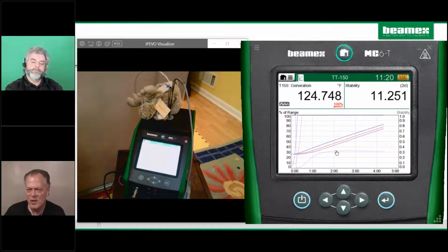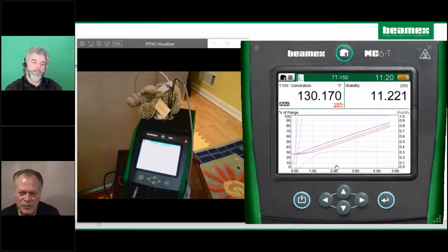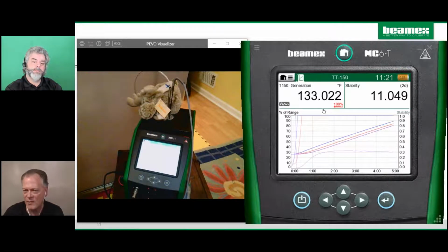So we've been talking now for 4 minutes since we made that first recording, and we're getting there. We're now seeing 100% on the graph. We're at 100, almost 130 degrees. So everything's moving along pretty good. We should see this start to level off somewhere around 145. So we're giving it 100% heat right now. We're giving the insert as much heat as we can deliver with the dry block here.